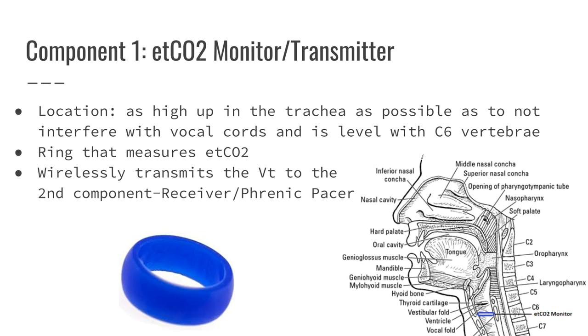Component 1. In order to get an accurate end-tidal CO2 reading, it must be able to measure all the air that the patient exhales. Traditional capnography uses a round tube that all the air must pass through, hence why this is in the shape of a ring, as you can see here in blue.